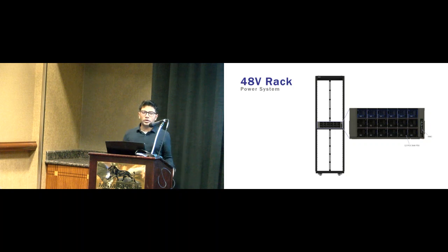So one of the challenges or newness in consuming this platform is that it's an Open Compute platform, and that's not a big deal. Open Compute has been deployed for a long time, right? This is a 48 volt system, so you need a 48 volt rack, and we need a 48 volt power shelf as well. The early 48 volt power shelves available today come with something called a battery backup, essentially, that way of doing things.